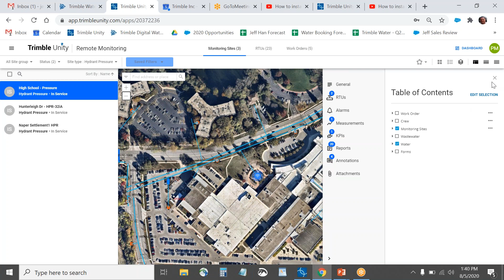To look at the data, I can see that this is the high school pressure site. It gives some basic information, but most importantly, it tells me the last time it received data was August 5th, and the next scheduled call is August 5th, in an hour. So this is actually calling every hour. Most are set up to call every day, but this call schedule is very user definable.